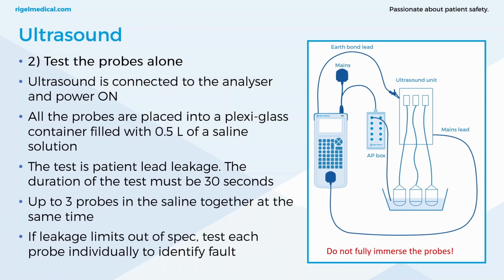So if we think about this from the application of ultrasound in the setting, a clinician uses ultrasound gel. That gel is water-based and it's conductive, and it's designed to remove air, which is an insulator, so that ultrasound waves can travel easily between the body and the probe. Now, if you imagine that the insulated casing of an ultrasound probe became cracked, then gel could ingress into that circuit where you've got the potential of current flowing to the patient.